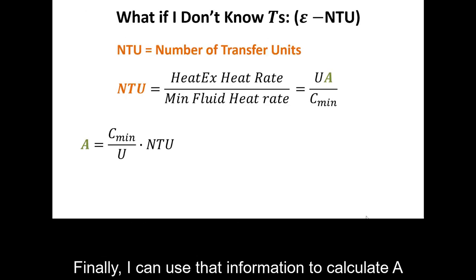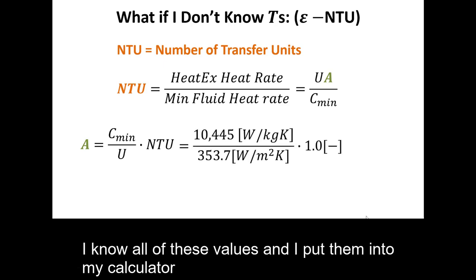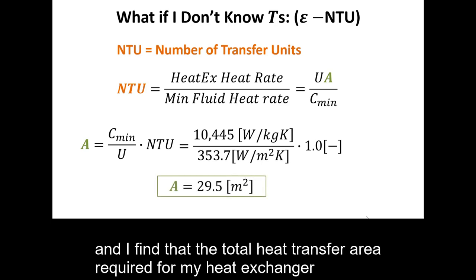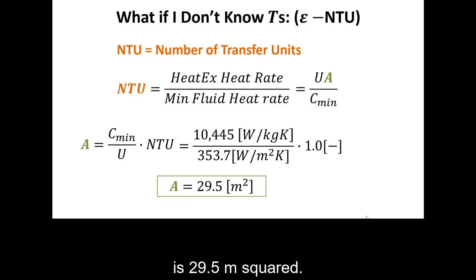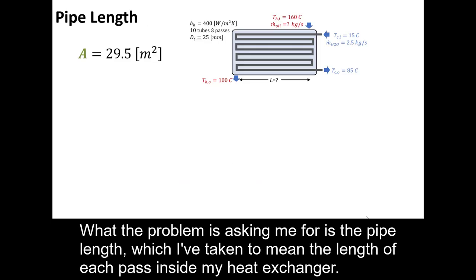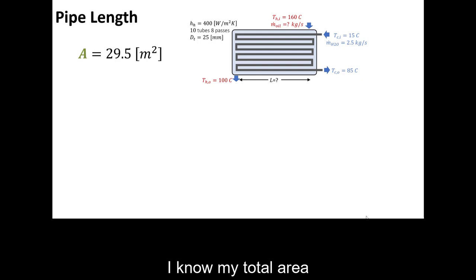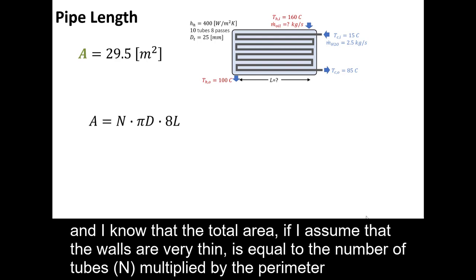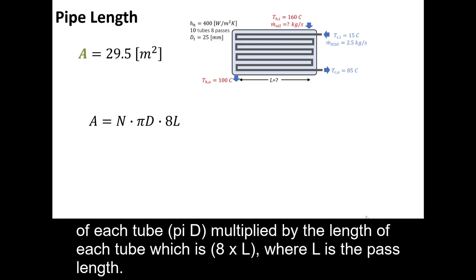With all values known, I calculate the total heat transfer area required: A = NTU · C_min / U, and find it is 29.5 square meters. The problem asks for pipe length, specifically the length of each pass. The total area equals the number of tubes n, multiplied by the tube perimeter π·d, multiplied by the total tube length per tube, which is 8 times L, where L is the pass length.